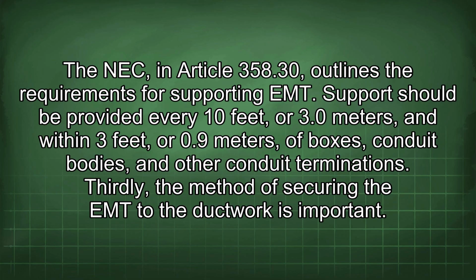The NEC in Article 358.30 outlines the requirements for supporting EMT. Support should be provided every 10 feet, or 3.0 meters, and within 3 feet, or 0.9 meters, of boxes, conduit bodies, and other conduit terminations.